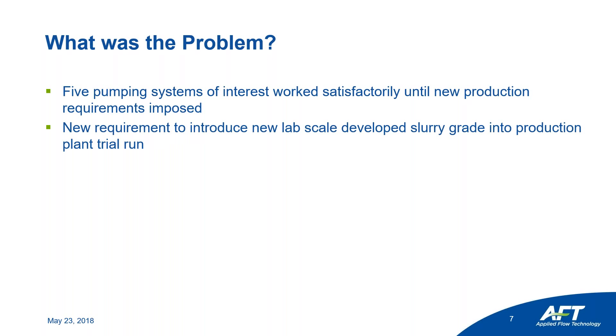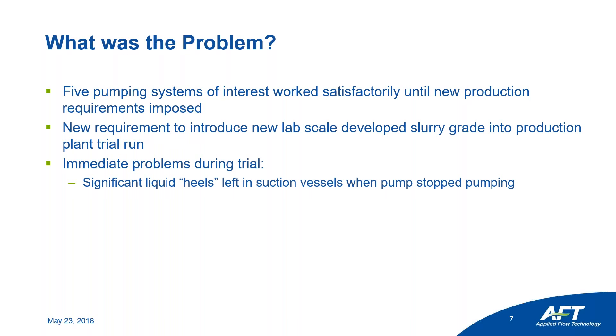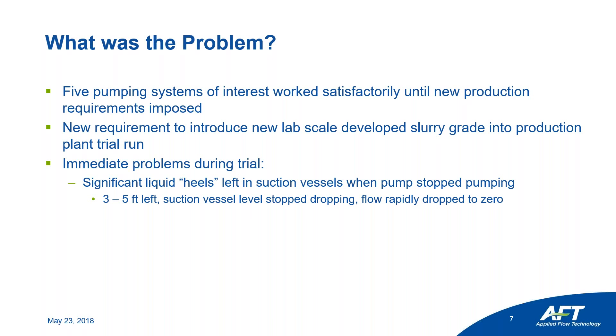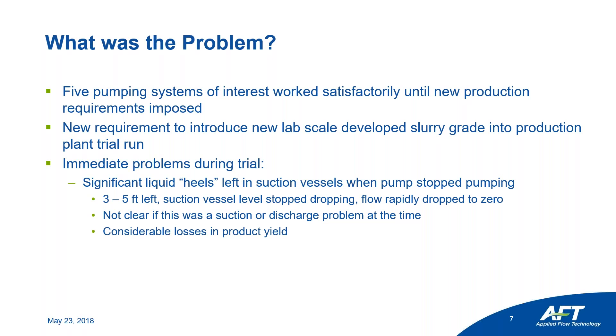The problems they experienced included significant liquid levels left in the suction vessels — three to five feet high — when the pumps stopped working. The suction vessel liquid levels stopped dropping, the fluid just sat there, and flow rate through the piping system went to zero. They weren't sure if the problem was on the suction side or the discharge side. Overall, the amounts of liquid left over caused significant losses in product yields, and their flow rates were not adequate for production demands.